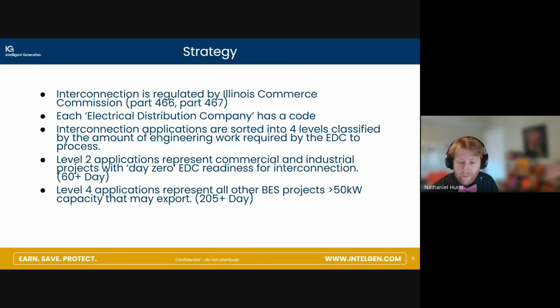I can count on one hand the number of large projects I've gotten through on a level 2 interconnection, mostly just 250 kilowatts of solar, stuff like that. It's very, very challenging, even if you do everything perfectly right, to have a site that's eligible for level 2 interconnection. So level 4 applications represent all other BES projects. They typically exceed the 6-month timeline: 25 days setup time, 6 months execution time. And it's sort of just the beginning of the whole dance there. Can I have the next slide, please?